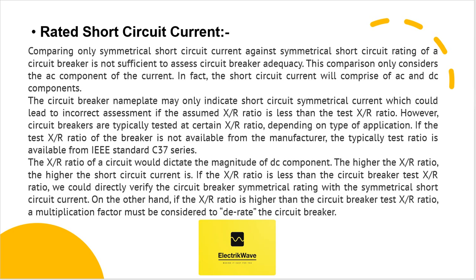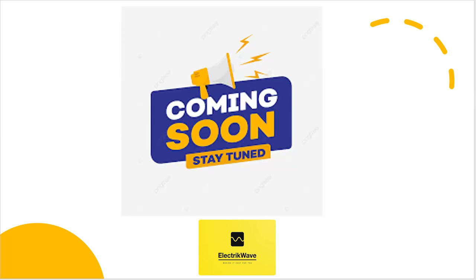On the other hand, if the X by R ratio is higher than the circuit breaker test X by R ratio, a multiplication factor must be considered to derate the circuit breaker. Stay tuned — we will discuss other technical topics in upcoming videos.